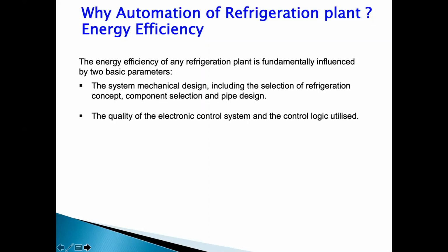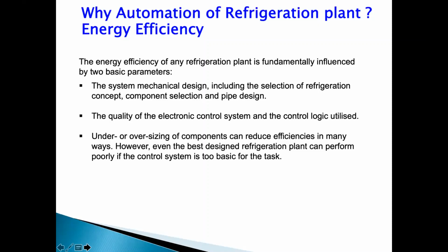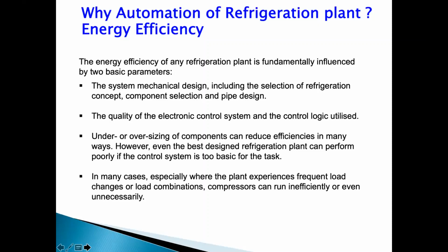Of course, the quality of control system and control logic used decides the efficiency of the plant. When you are designing, too much over design, sometimes people say, okay, let's design by 20%, 25% more. That costs money in terms of initial cost, and also costs money in running cost and unnecessary expenditures. Whereas sometimes you under design the plant and then you spend money on longer running hours, and sometimes you don't get the achieved temperatures. Your product temperatures are not achieved. So all this needs to be understood and finalized. As I told you, the loading and unloading of the plant.